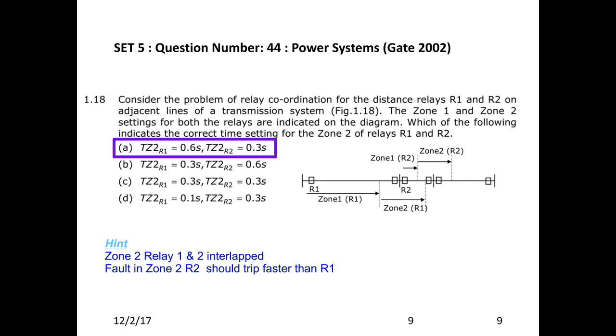The timing for Zone 2 of R2 should be lesser than Zone 2 of R1, so choice A is correct. Generally, relay coordination is done in two ways: the time graded principle, where incremental time settings are applied to the faulty system, and the current graded principle, where current settings are set at incremental values.